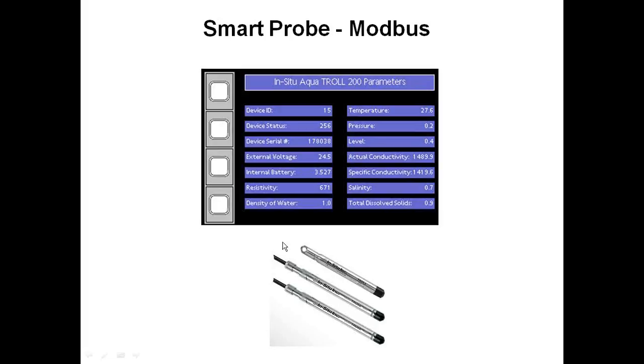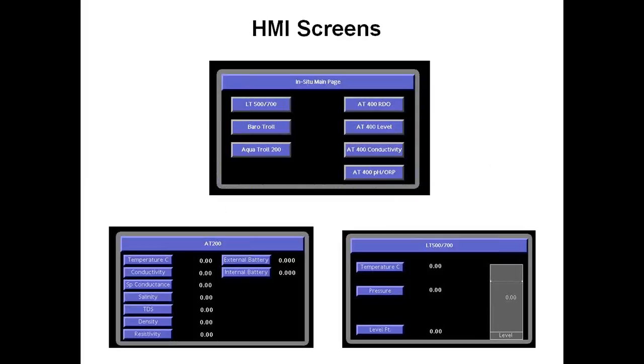As you're dealing with different probes out there, we've done a lot of work with a company called In-Situ, though there are others doing level probes. In-Situ has one that does Modbus and analog — what we're showing here is one of these probes. We can come out of it with 2 wires to one of our serial radios, then pull all the data out of the registers internally on that probe. These are other screens we built where they had different probes and wanted to view different information. C&E does a lot of HMI work, and with our radios and Modbus/Ethernet, it's very easy to collect your data and get it into this kind of format.